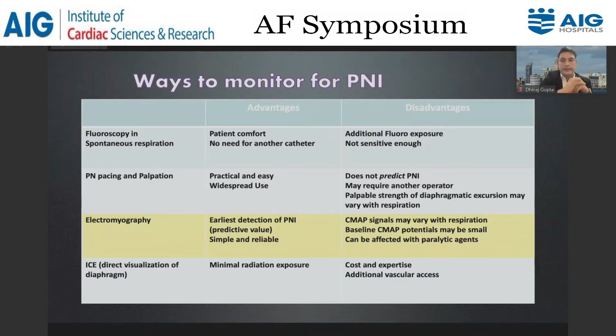Monitoring rate of temperature drop is extremely important. So almost as important as looking at the signals on the Achieve, you need to closely monitor the temperature drop on the console. If your temperature drop is too rapid, then that can be a sign to you that you are inside the vein and you're likely to cause damage to extracardiac structures. For example, this study showed that if you reach a temperature of -38 degrees Celsius or lower at 40 seconds, then that can predict phrenic nerve injury with a high sensitivity and specificity. So the important thing is -30 degrees at 30 seconds is good.